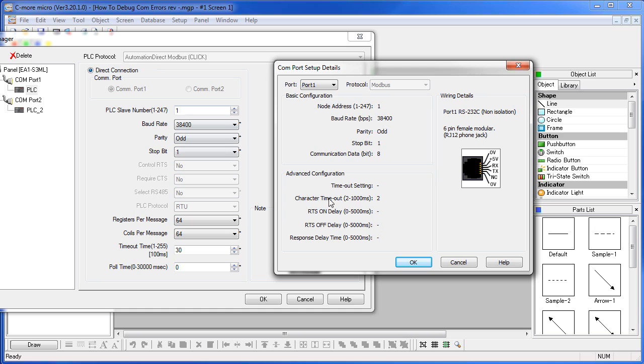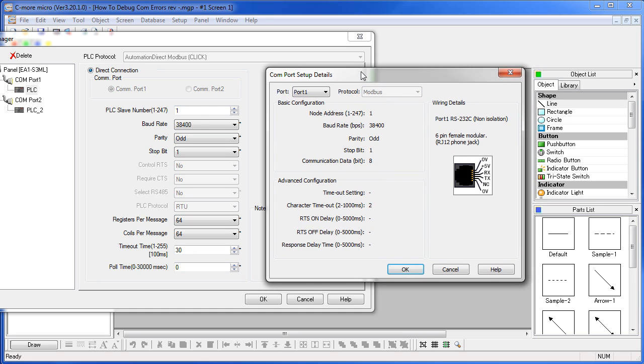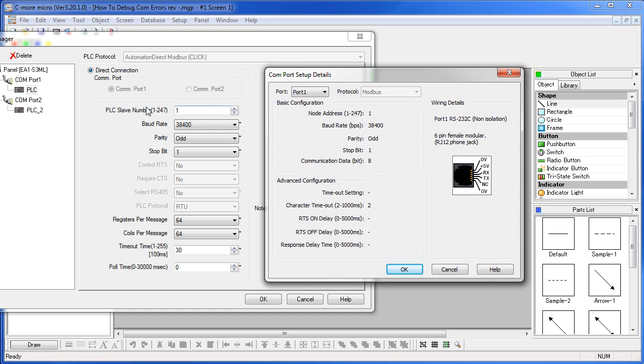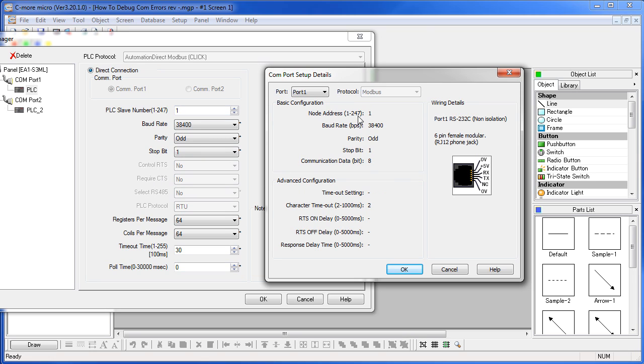So, here is our panel, here is our PLC. Comparing side by side, we see that they are both operating on the same address 1, same baud rate, same parity, same stop bit and 8 communication bits which are assumed over here on the panel. So, my panel serial port settings match my PLC serial port settings. So we should be good to go.